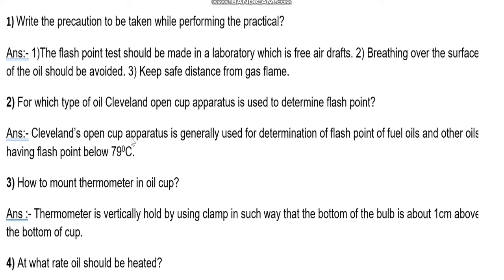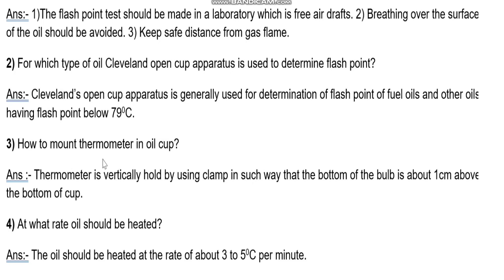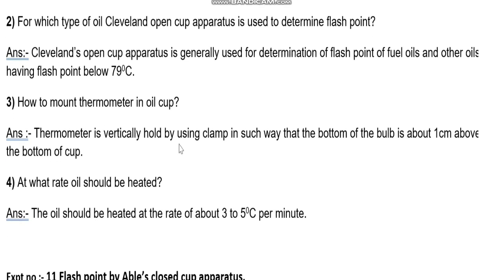Second question: for which type of oil is Cleveland's open cup apparatus used? Cleveland's open cup apparatus is generally used for determination of flash point of fuel oil and other oils having a flash point below 79°C. How to mount the thermometer: it is held vertically using a clamp so that the bottom of the bulb is about one centimeter above the bottom of the cup.